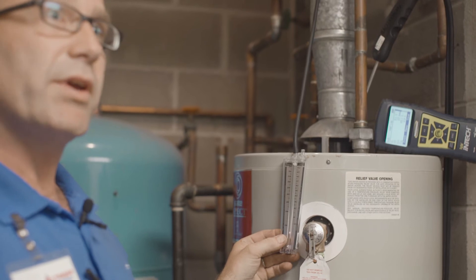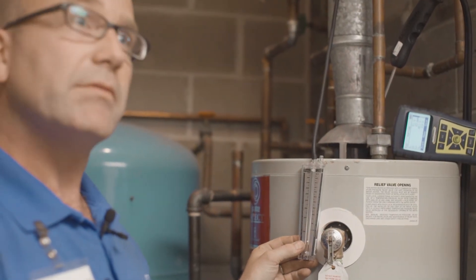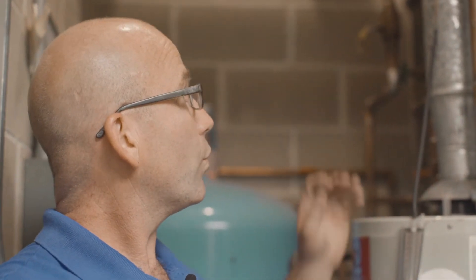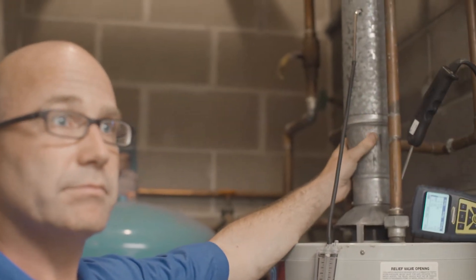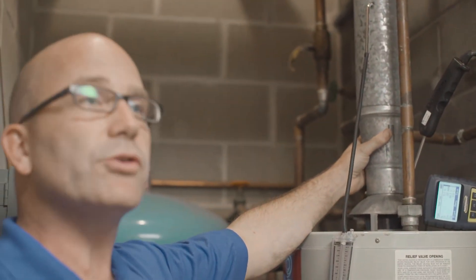If this draft gauge, if the bubble inside this isn't at a high enough level, that means either one of two things: we don't have enough air to support combustion or our chimney is blocked. It's that simple. That's what good draft means.